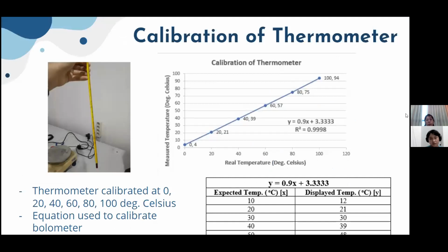Next. So for the calibration of the thermometer, we want to make sure that the thermometer was actually working well. So we calibrate it at 0, 20, 40, 60, 80, and 100 degrees Celsius. And then we want to obtain the linear regression, which is in here, the Y. Why we want to get the linear regression is so that we could use it to calibrate the bolometer.